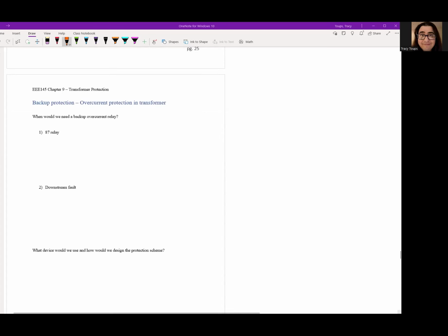Okay. So that pretty much covers differential protection as a whole, including all the one-off cases we just talked about. But remember our rule of thumb, anytime we have protection, we should have an overall primary protection, which is 87 differential, but we always need a backup protection. And it's always good practice to have a different type of backup protection than the first one. So if we use 87 for primary, it's good to have a non-87 relay as backup, just in case for some random fluke in the system, the 87 relay is unresponsive. So naturally, we can turn to an overcurrent relay.